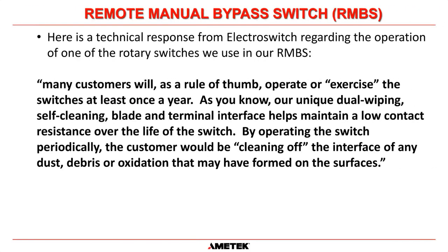And this slide is actually a really good example of what the manufacturer recommends. This is an email that we got from one of the engineers from ElectroSwitch, and ElectroSwitch is one of the companies that manufacture our RMBSs. And they said, many customers will, as a rule of thumb, operate or exercise the switch at least once a year. And he goes on to say, as you know, they have a unique dual wiping self-cleaning blade and terminal interface, and that helps maintain a low contact resistance over the life of the switch.